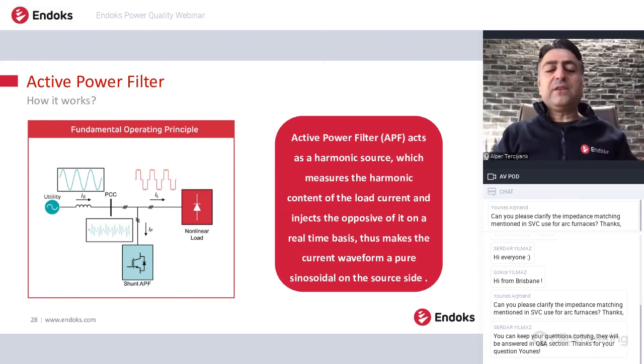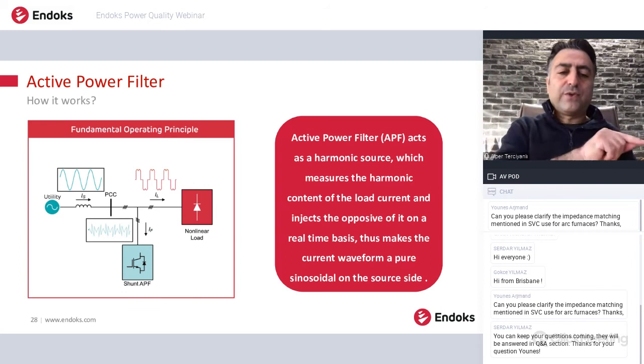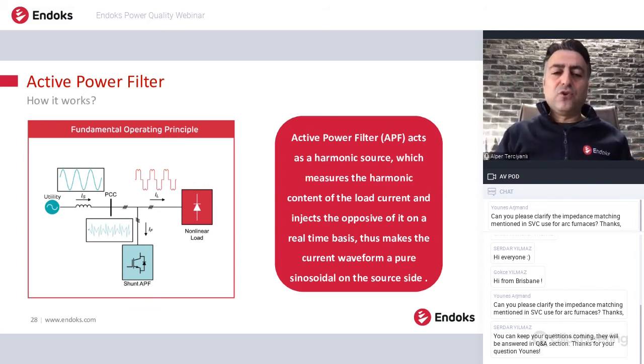But an active power filter can also work like a STATCOM. It can inject harmonics and reactive power together at the same time. So an active power filter can work as a STATCOM and also can eliminate the reactive power. In low voltage applications, we are mostly using three-phase, 4-wire shunt active filters. The 4-wire means the neutral conductor. So by using the active power filters, we can also eliminate triplen harmonics and the unbalance on the system. We can also eliminate the neutral currents on neutral conductors by the active filter. It's a good thing if we can avoid the neutral currents.